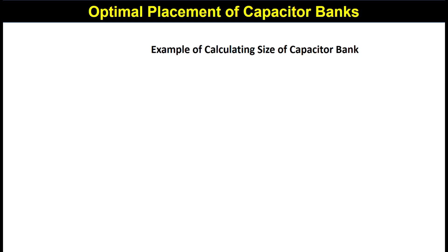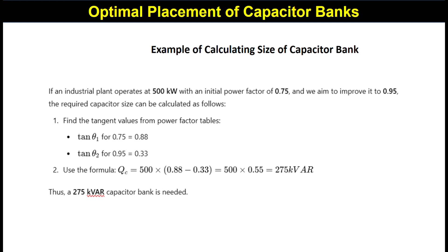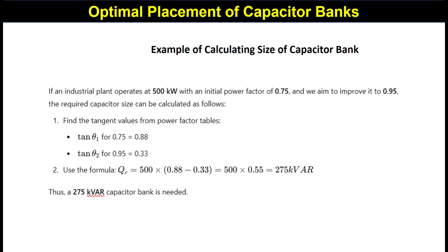Now we will take a simple example using this formula. An industrial plant operates at 500 kW with an initial power factor of 0.75, and we aim to improve it to 0.95. We first find tan θ1 for a power factor of 0.75, and tan θ2 for a power factor of 0.95, which gives a value of approximately 0.33.